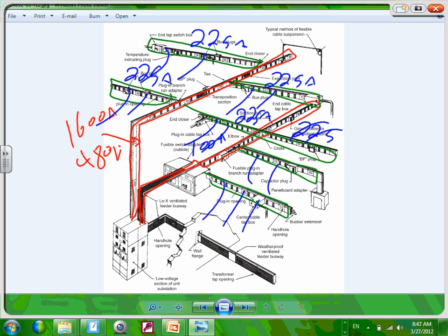And right in here, the feeder itself will have, feeder number 2, what is it, 1000 amp? Feeder number 2 is actually 1600 amp. Feeder number 2, which is 1600 amp right here, will have a 1600 amp circuit breaker protecting it. Can I get you guys to understand that feeder number 2 here is a 1600 amp feeder? You have a 1600 amp circuit breaker protecting it. And then you continue all the way. Then you come over here.